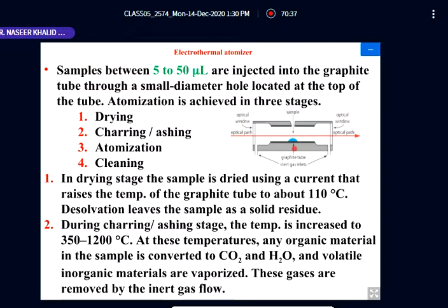We can't use any detergent here, for example, like dishwashing. No, we can't use any liquid, chromic acid. No, we can't use any solid material such as Vim or Surf. So within the instrument we can clean this, and we can get rid of the residual components which are present.